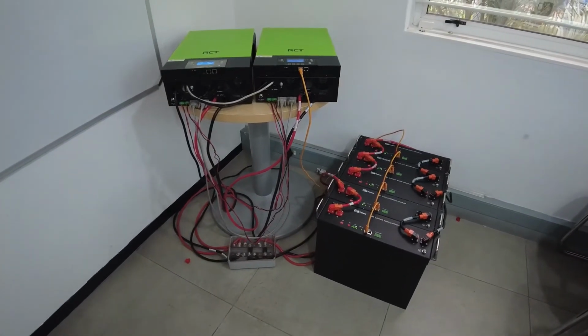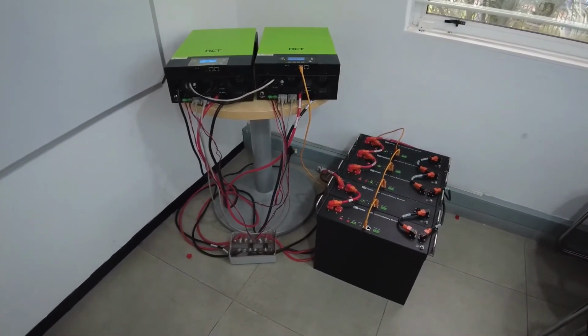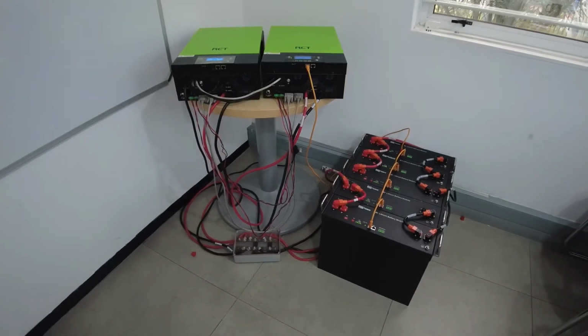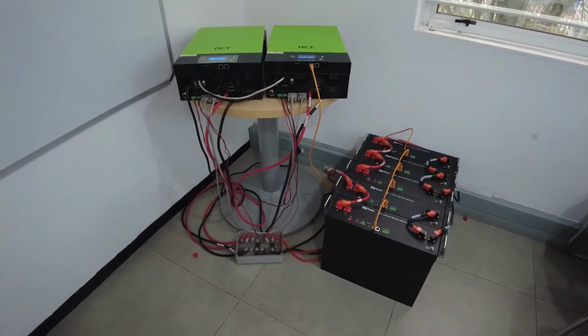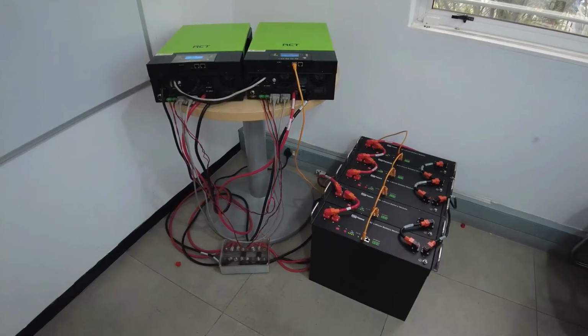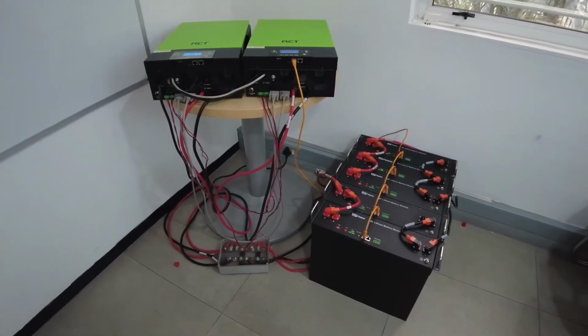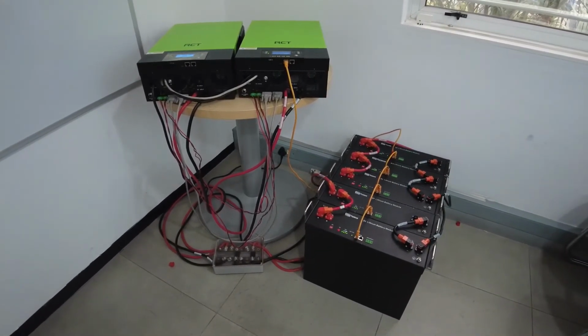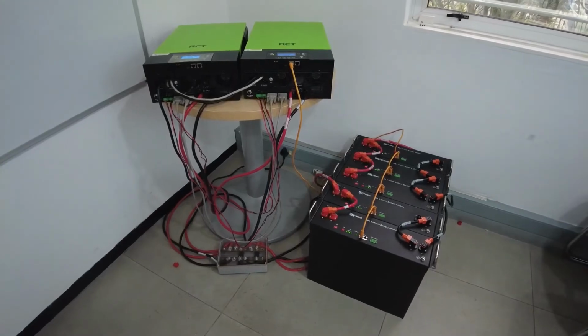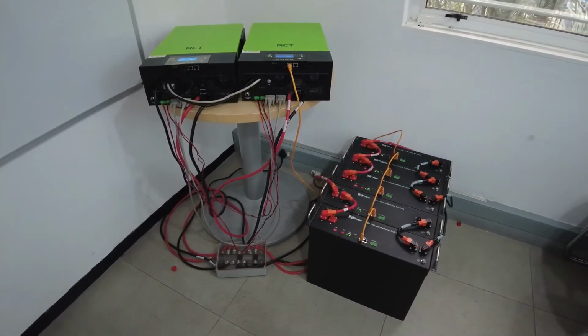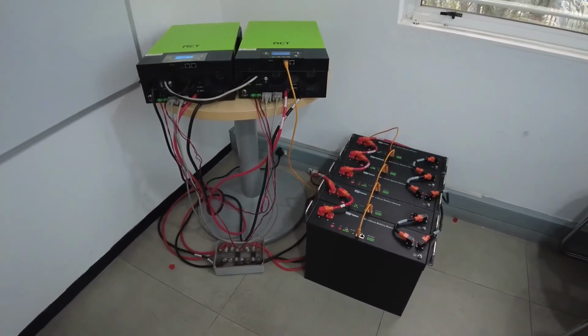Okay, that is it. The two inverters are connected in parallel. They're communicating with one another. The one inverter is set up to communicate with the master battery, and obviously the master battery will communicate with all of the batteries it's connected to. All is communicating, all is up and running, all is ready.